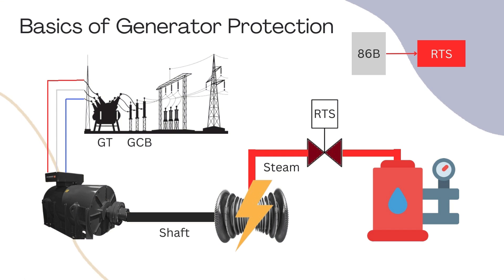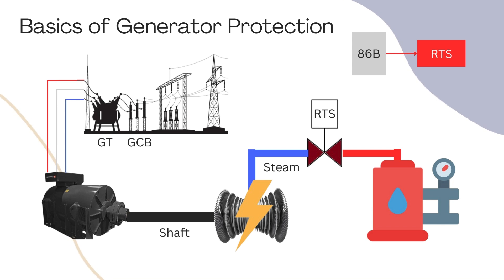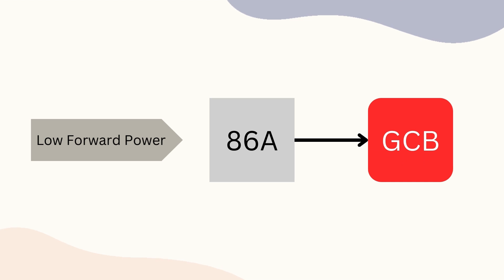If a fault occurs in the turbine, Class B protection will operate. The relay will send a close command to the RTS valve to stop the steam flow to the turbine. Despite this, some kinetic energy will keep the rotor rotating for a while and generate power. This lower power generation will activate the low forward power relay, which will send a command to the Class A relay (86A), tripping the GCB to isolate the generator from the grid.